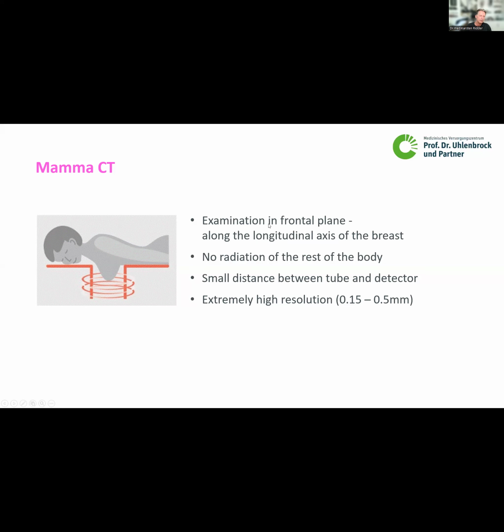You have an examination in the frontal plane at the longitudinal axis of the breast. The patient is in prone position, the breast hanging free in an opening, and the technique is under the table. You have no radiation of the rest of the body, and you have a small distance between the tube and detector, and therefore an extremely high resolution down to 0.15 millimeter for the ABCT in an isotropic voxel.